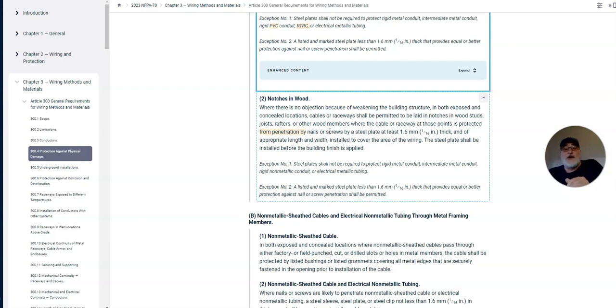Steel plates shall be installed before the building finish is applied. Basically, that is before the sheetrock goes on. Okay. You'll see that the steel plates in exception 1 are not required to protect rigid metal, IMC, rigid non-metallic conduit, or EMT. And it goes on to talk about the listed and marked steel plate not less than 1/16 inch thick that provides equal or better protection against nail and screw penetration shall be permitted.